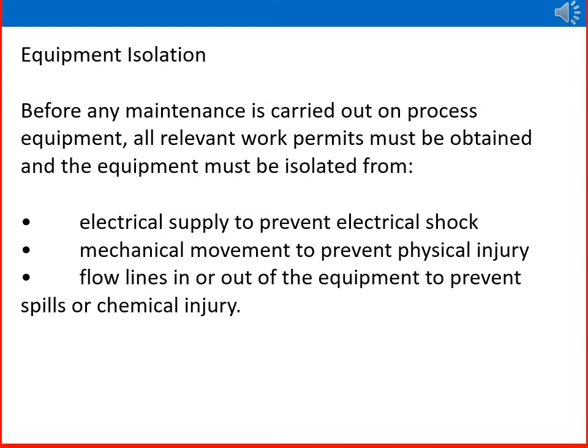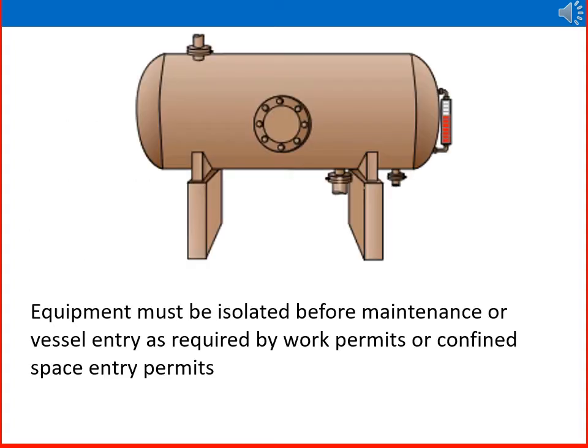Before any maintenance is carried out on process equipment, all relevant work permits must be obtained and the following must be isolated: electrical supply, to prevent electrical shock or hazard; mechanical movement, to prevent physical injury; and flow lines in or out of the equipment, to prevent spills or chemical injury. Equipment must be isolated before maintenance or vessel entry as required by work permits or confined space entry permits.